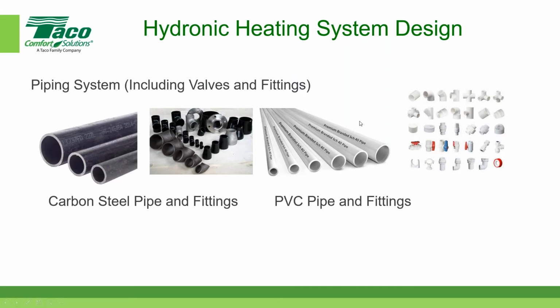And then on the right side, we have Schedule 40 PVC pipe. Again, I'm just demonstrating a general category of plastic pipe. There are all kinds of materials out there in the industry today, such as PEX tubing, polyethylene cross-link, and PVC, as we've shown here. The type of material that you ultimately select for your system will be based on a variety of variables: the cost of the material, the temperatures, the pressures, and whether or not it's compatible with the fluid that you're using. Since we're talking mostly HVAC systems, the majority of available materials are usually compatible, because for the most part, HVAC systems use either water or water glycol solutions as the working fluid. Okay, the next category would be boilers.